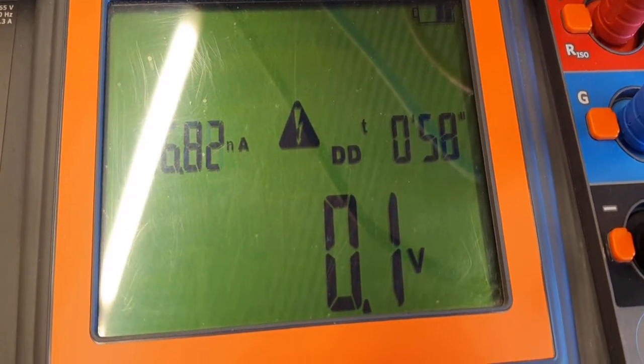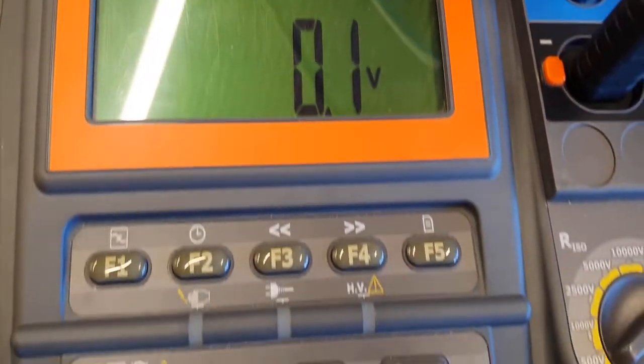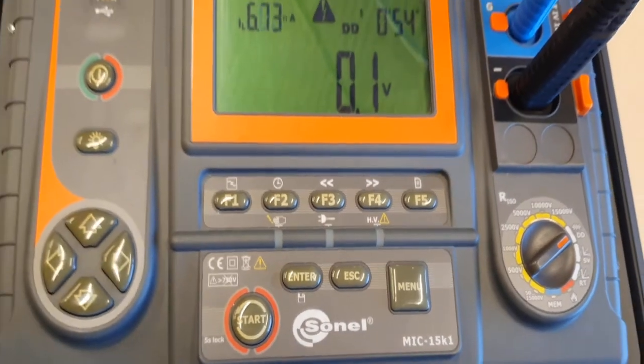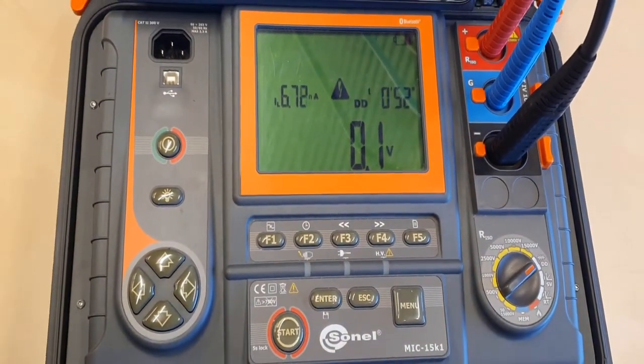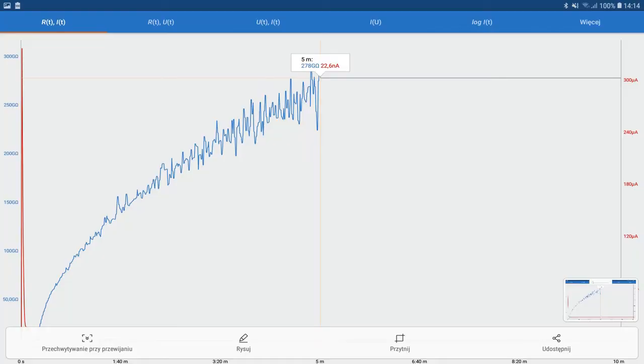As a result of the measurement, we get the following graphs, available in the mobile application, but you can easily download it. The first waveform is the resistance in time, it's a blue line, and the current in time is a red line. The current initially is high during the charging, later is very small.